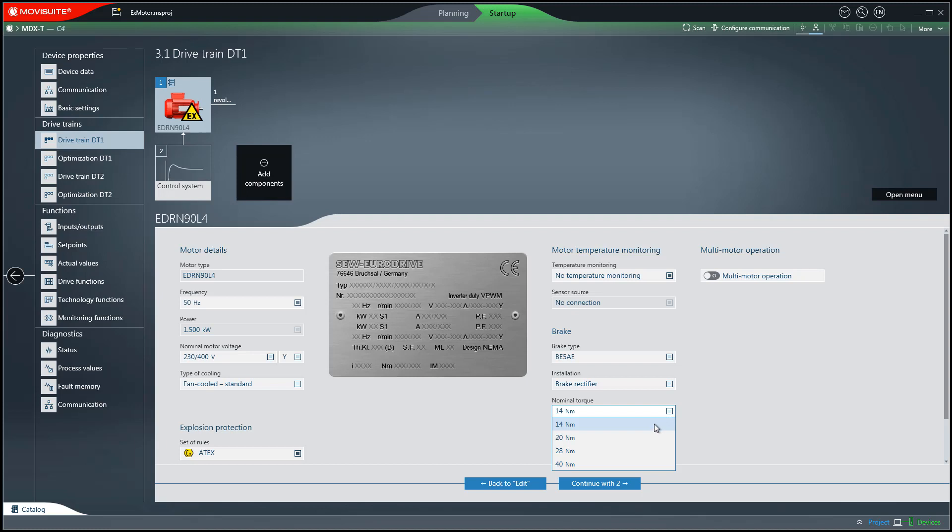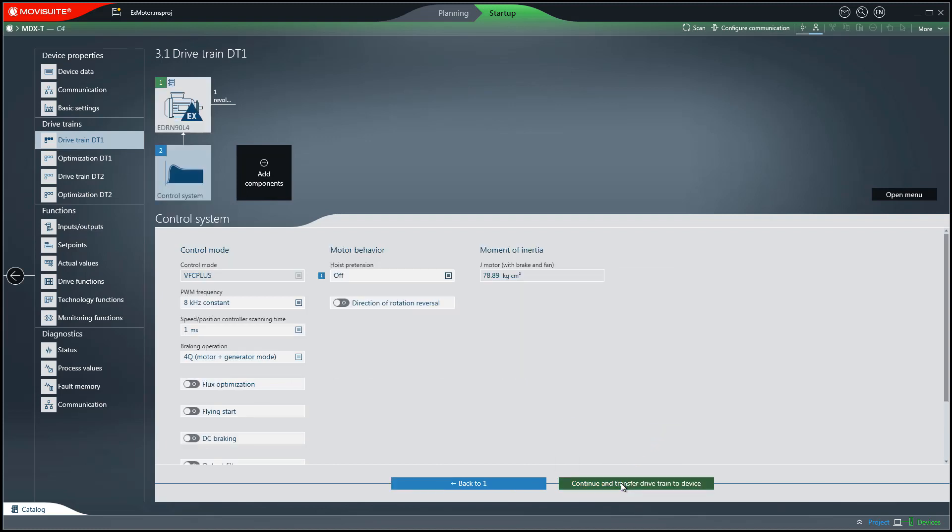The continue with two buttons takes you to the controller settings of the drive. The VFC plus control mode is fixed set for asynchronous motors and the CFC control mode is set for synchronous motors.